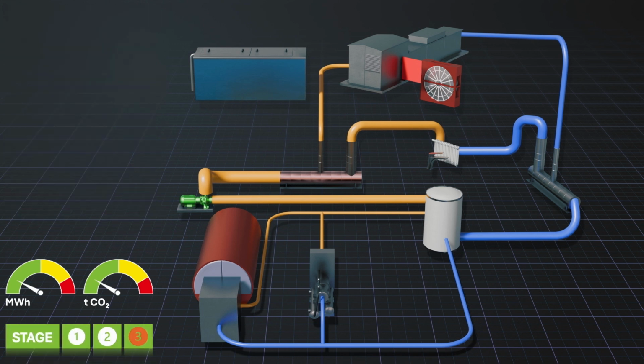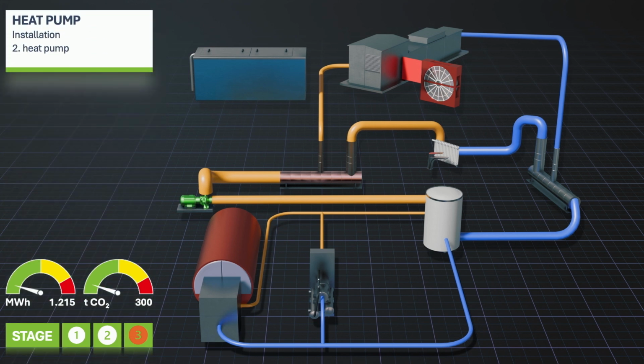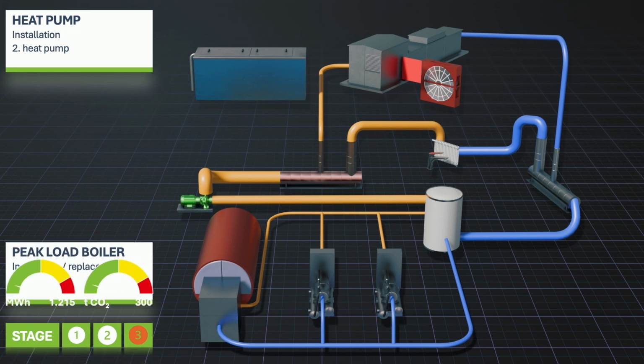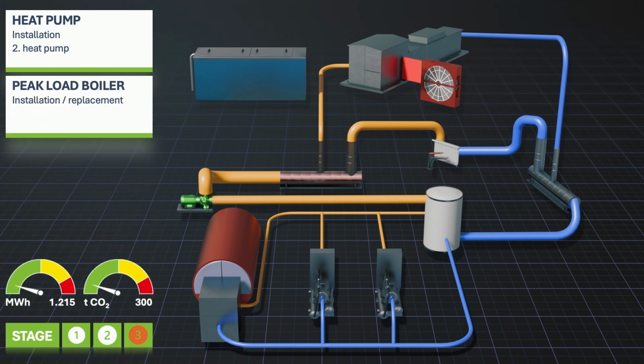With the third construction phase, the heating system achieves almost complete CO2 neutrality. A second heat pump takes further operating hours away from the gas boiler. In addition, the third gas boiler can now be replaced with a modulating burner to meet demand. As a result, this gas boiler only runs for a few hours a year, as shown by the blue section on the right of the diagram. Alternatively, it can also be operated with hydrogen.